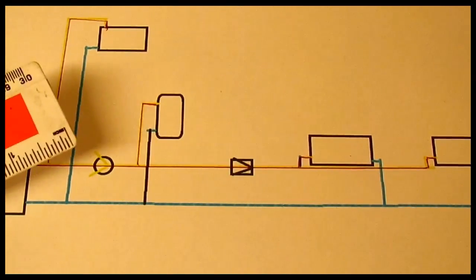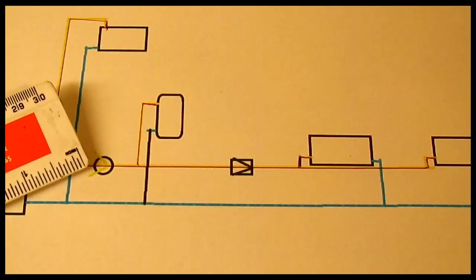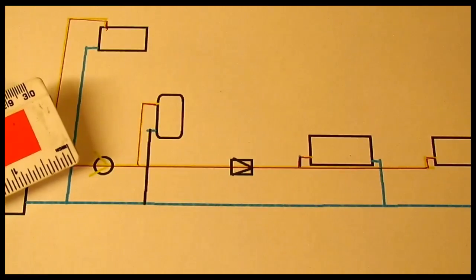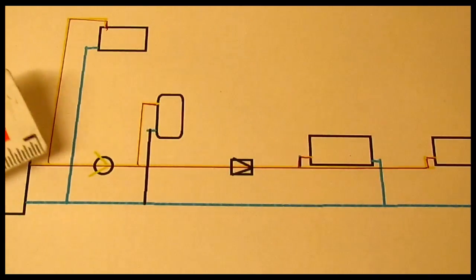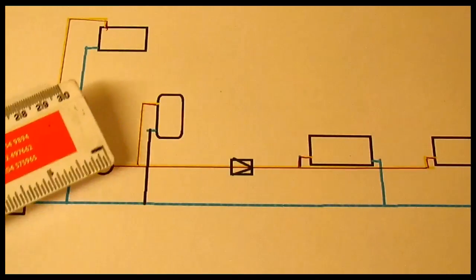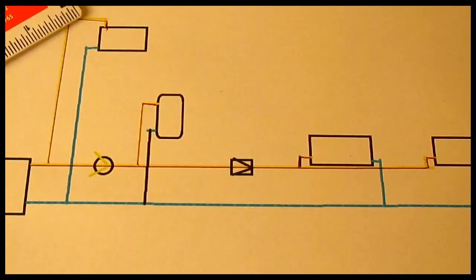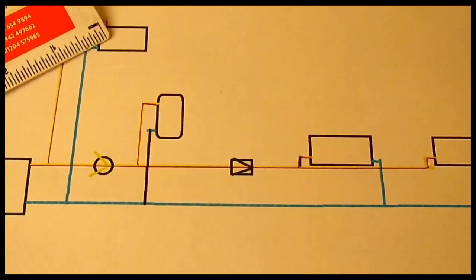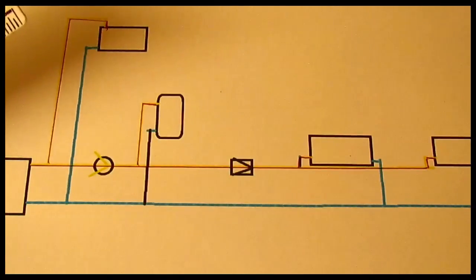So this is the first stage of the evolution of central heating — where we've got a boiler, a pump, and a valve. What was happening now is that when the valve shuts down and the central heating goes off, we've shortened the circuit. The pump is going through the cylinder and back to the boiler but it's now only on a short circuit, where it had a long circuit before. This causes problems with over-pumping into the tank — it would make like another radiator in your attic, with steam coming out and it being warm up there. Nobody knew how to stop it, so that's when we started looking at other ways of piping things up.